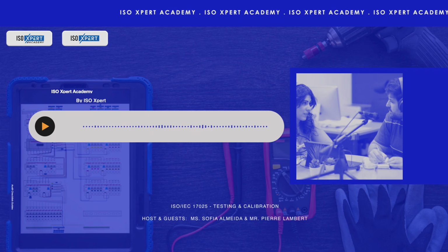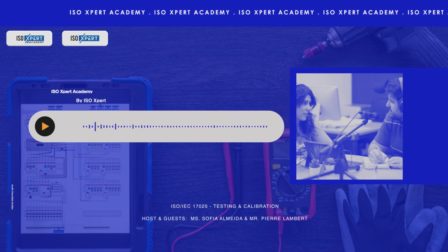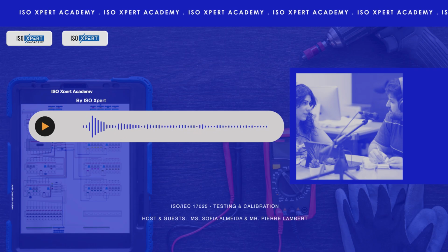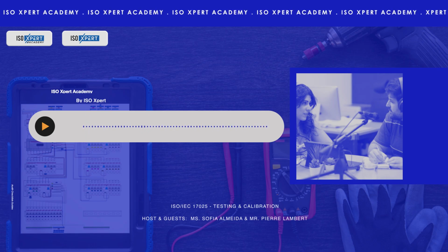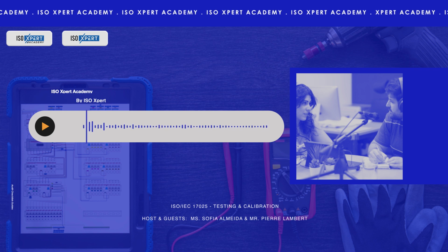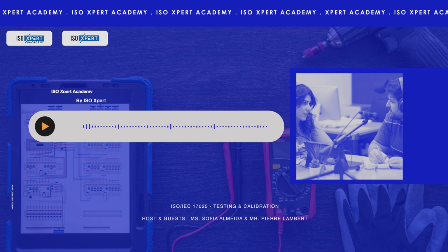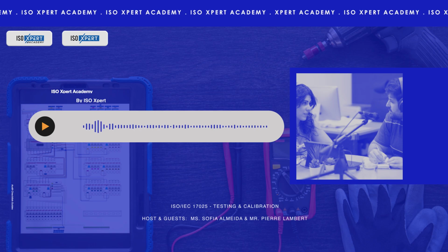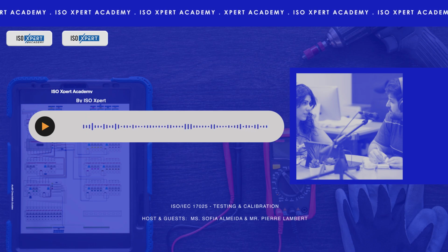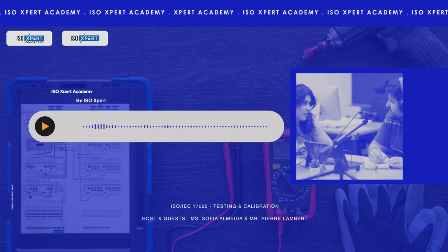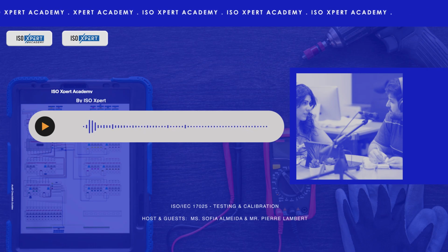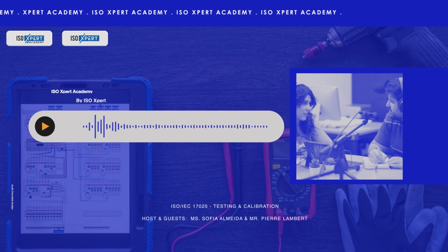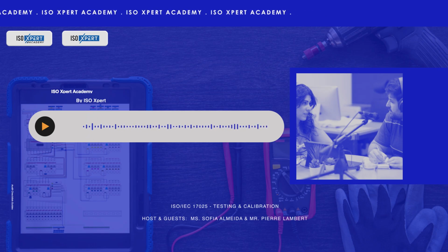Okay, all that careful work generates data. Records. What are the requirements there? Clause 7.5, technical records. All test and calibration records must be complete, accurate, and fully traceable. Traceable meaning you can follow the whole process. Yes, you can see exactly what was done, when, by whom, using which equipment, under what conditions. These records form a robust, verifiable history of the work. What kind of records are we talking about? Could be detailed test reports, carefully maintained lab notebooks, maybe securely stored digital records from instruments or LIMS systems. The key is they must be retrievable and understandable, even years later if needed.